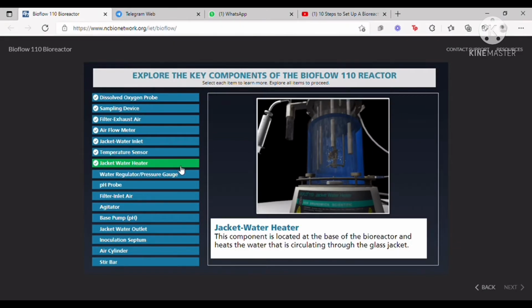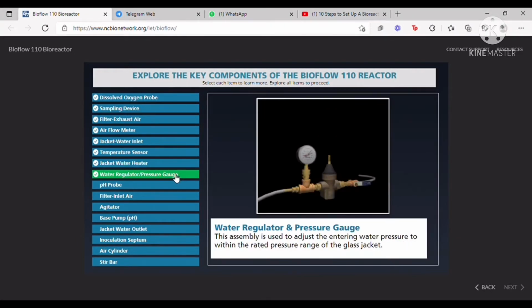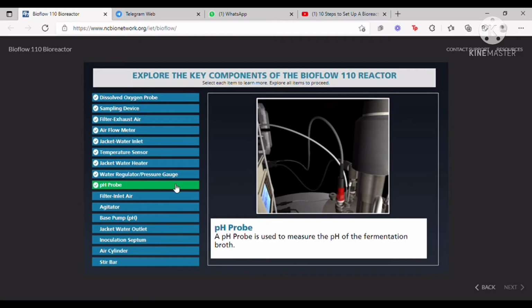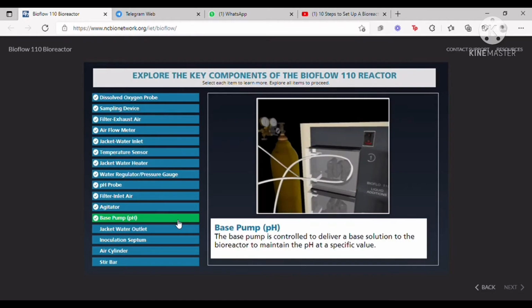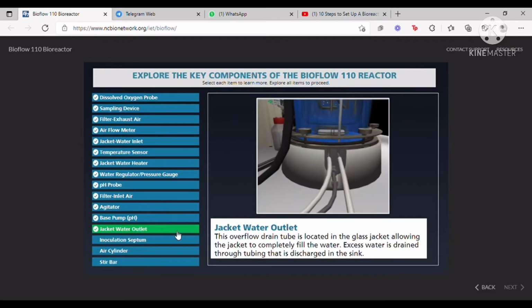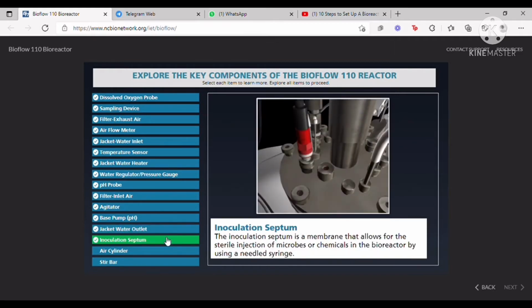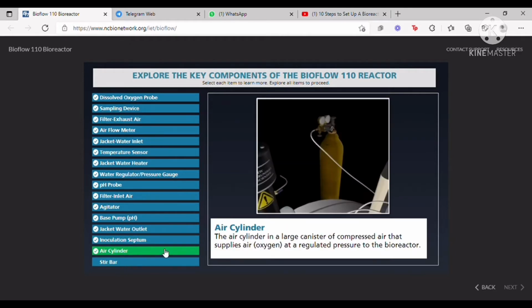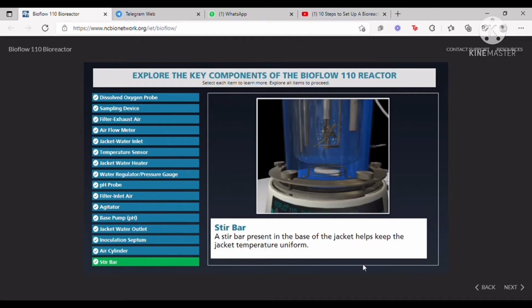Next would be the jacket water heater. This component is located at the base of the bioreactor and heats the water that is circulating through the glass jacket. Next, the water regulator and pressure gauge. This assembly is used to adjust the entering water pressure to within the rated pressure range of the glass jacket. Then the pH probe used to measure the pH of fermentation. Next would be the agitator that ensures proper mixing, the base pump, the jacket water outlet that's located in the glass jacket, the inoculation septum, a membrane that allows sterile injection. Then we have the air cylinder, a large canister, and lastly a stir bar.